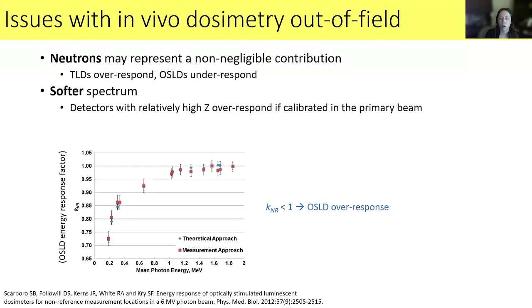Out-of-field dosimetry is especially relevant for implanted devices such as cardiac pacemakers and defibrillators, and also for pregnant patients. So both of these represent cases where there may be adverse effects associated with relatively low doses of radiation. And so accurate knowledge of out-of-field dose would be essential in those cases. TG203 covers cardiac devices, and TG36, which is a relatively old report now, covers fetal dose, and an update to that is in the works.